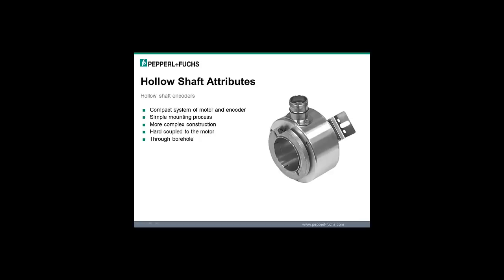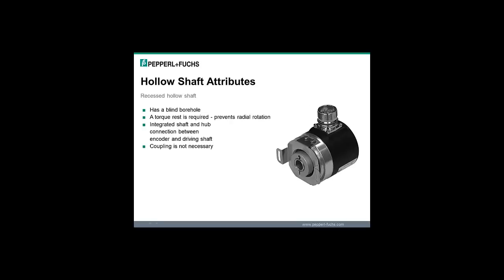The hollow shaft is more compact compared to the solid shaft. Because you don't need a coupler or mounting bracket, it makes the mounting faster and easier. The construction is more complex and is usually slightly higher in price compared to a similar solid shaft encoder. The hollow shaft has a hole completely through the unit, so it could be placed between other parts such as the motor and brake. A torque rest is required with hollow and recessed hollow shaft encoders. This prevents the radial rotation of the encoder.